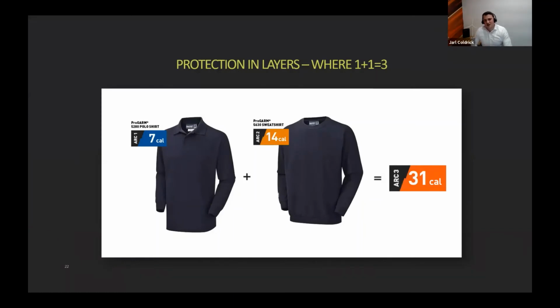Moving on to clothing systems: arc flash protection can be greatly enhanced when you're layering, so it's essential to layer up with the right garments. This illustration shows how a 7 cal polo shirt and a 14 cal sweatshirt can offer even higher protection. 7 cal plus 14 equals 21, but the combination of these garments actually achieves 31, because of the air gap between both garments. Air is a poor conductor of heat, so it acts as an insulator - that's why we say 1 plus 1 equals 3 when you layer up.